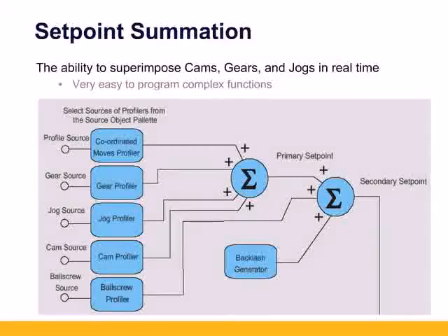I'm glad you asked. The heart of the ACR's advanced motion capabilities lies within the Setpoint Summation architecture. Each axis allows users to have multiple move types that can be commanded and with different sources. First, interpolated or coordinated moves use the trajectory calculated from the master. Second, you can also do gearing or following of another motion axis or an external encoder, or actually any ACR parameter for that matter. A common parameter for the Aries controller often used is a system clock, which is constantly running on power up. Third, single-axis offset moves can be commanded with the jog commands. The jog profiler calculates its own trajectory.